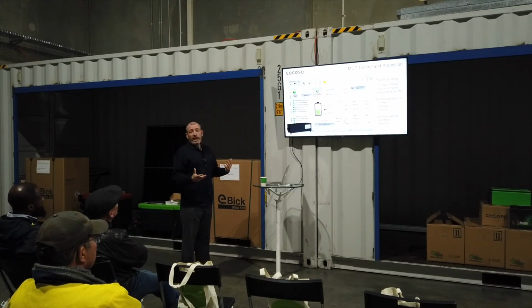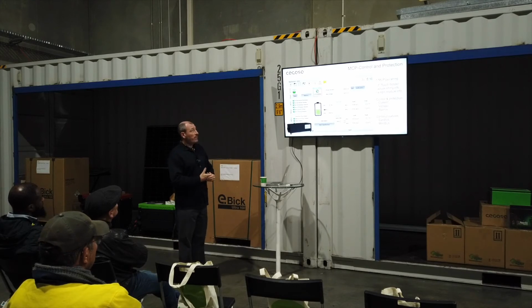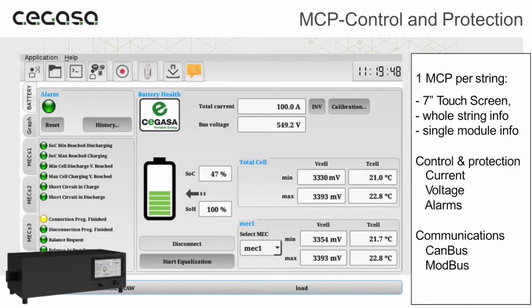What it's doing is acting like an external BMS, for the string, not only for the battery, but for the string, in the case we have many batteries. So it controls all the variables. It receives all the communications from every single module, and offers that data to the inverter in order to take the right decisions.